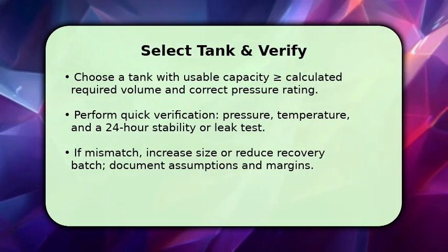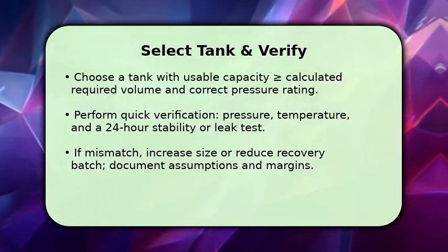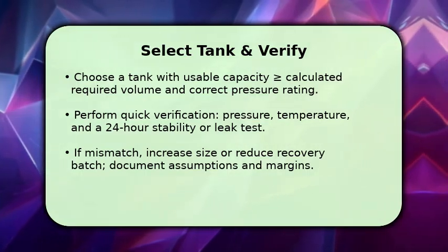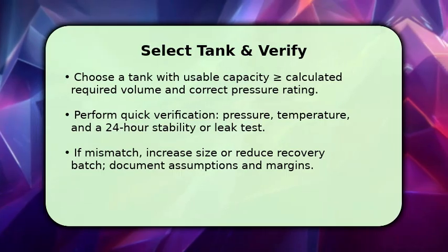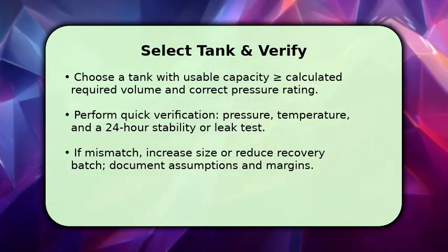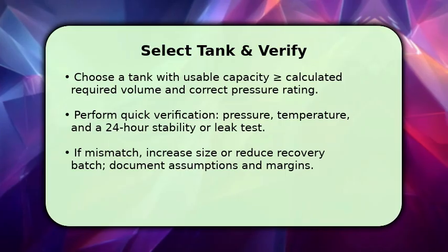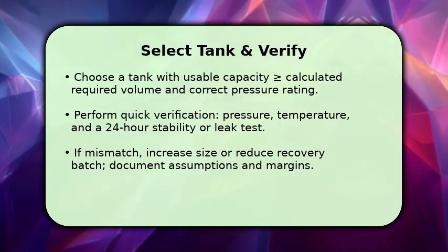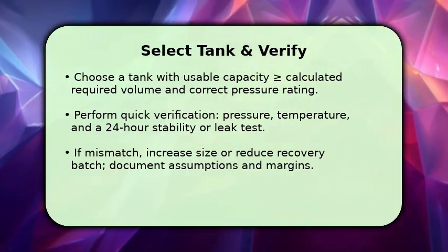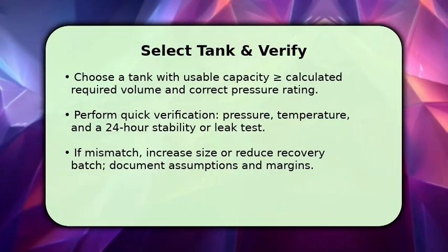ratings. Once installed, verify by a simple test. Fill to expected level, monitor pressure and temperature, and observe for 24 hours to confirm stability and no leaks.